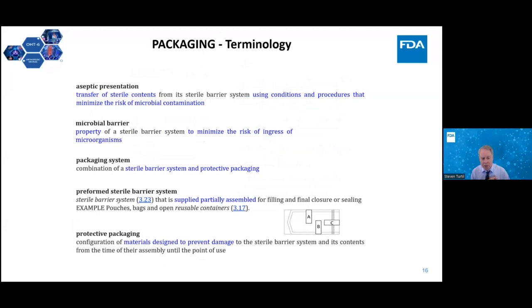A preformed sterile barrier system is a sterile barrier system that is supplied partially assembled already for filling and final closure or seal. There's an example given there, and you can see some manufacturers will buy a preformed sterile barrier system, and it'll include, for example, the seal A and seal B and the chevron seal. C is what the manufacturer will put it in. So in other words, they'll put a device in here, and then will seal it at the site of manufacture themselves. That's what a preformed sterile barrier system is.